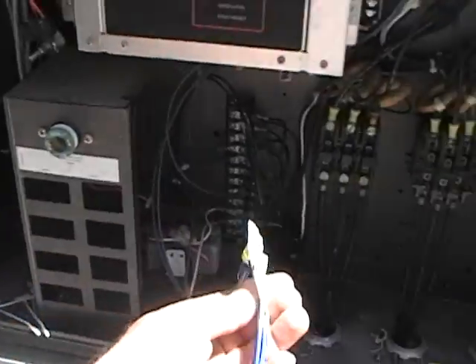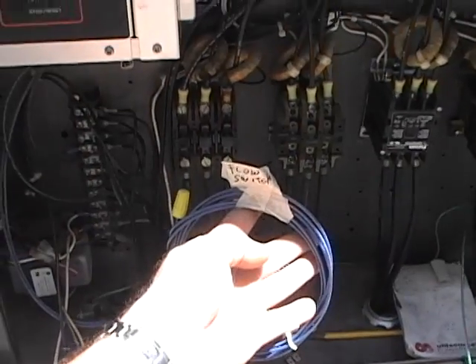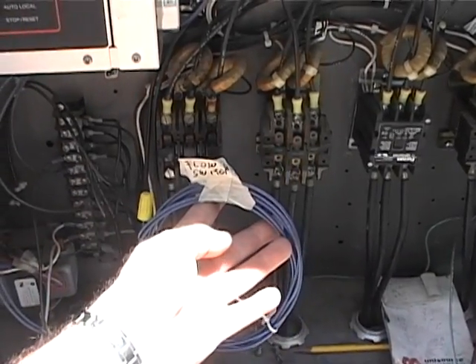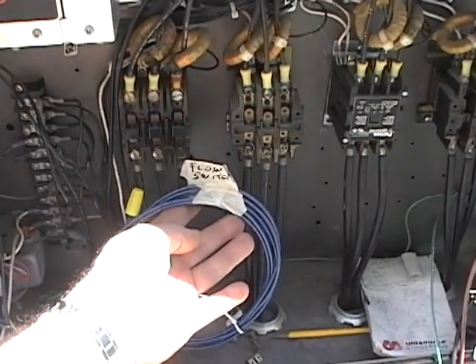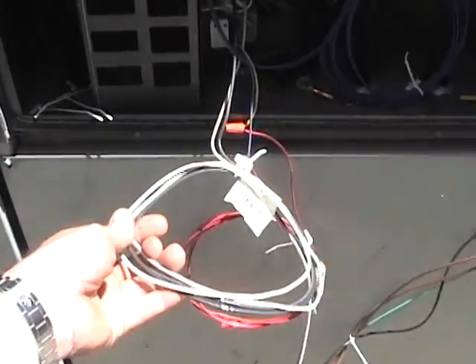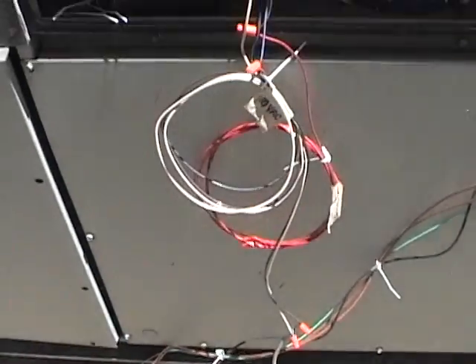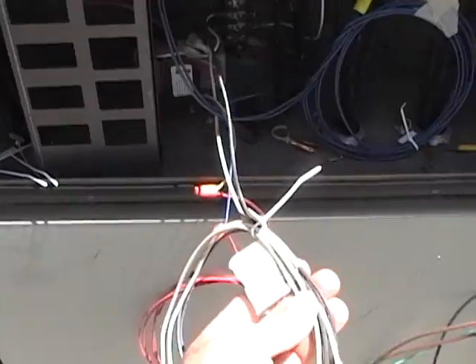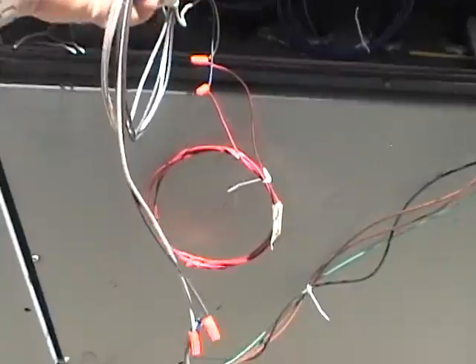The blue one right over here is marked flow switch. This is your external flow switch that you'll end up hooking up in order to make sure that the unit has water moving through it. And last but not least, it does require a 110 input for the actual control circuit. It doesn't have an internal transformer. So the black and the white wire are your 110 volt input. Okay?